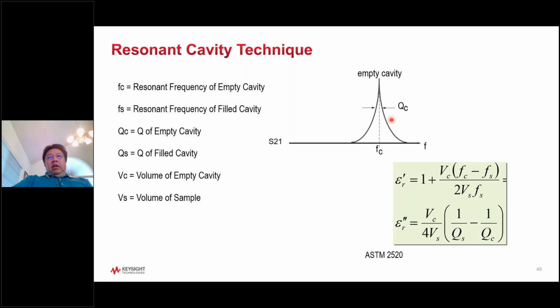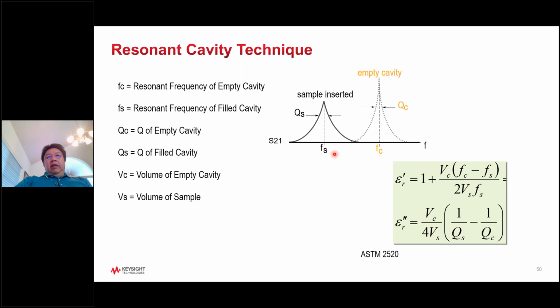Then we measure the empty fixture and the bandwidth or the Q, and then we insert the sample into it. Because the sample changes the Q, the bandwidth and the resonant frequency, we take the difference and use this formula to calculate the Dk and the Df value.